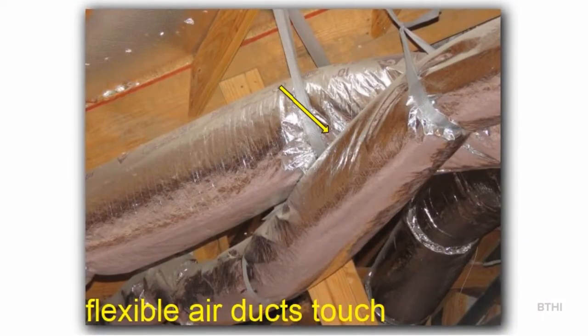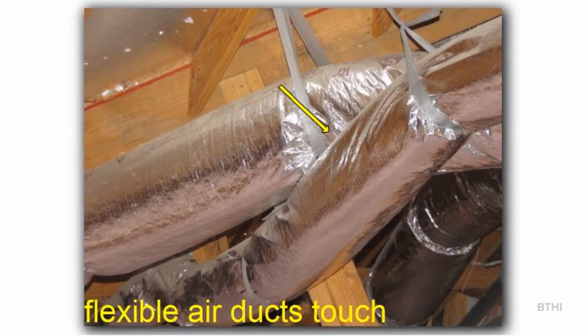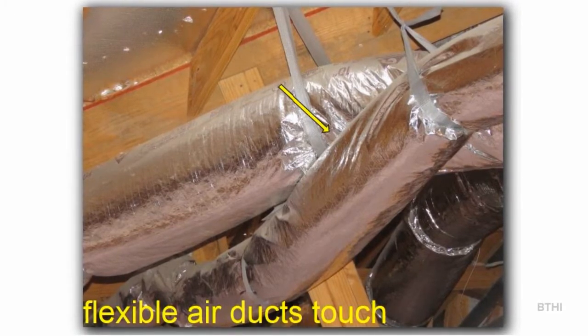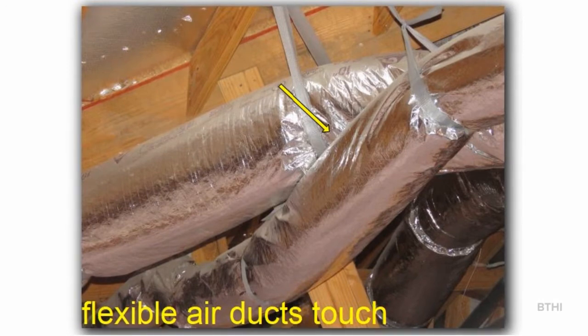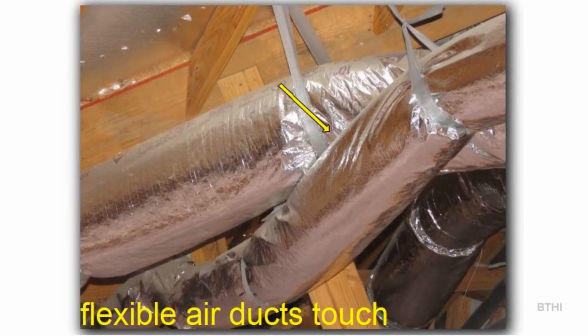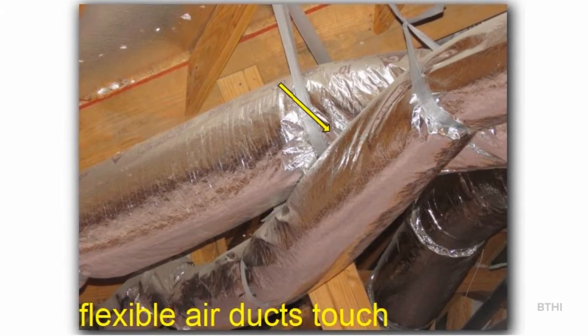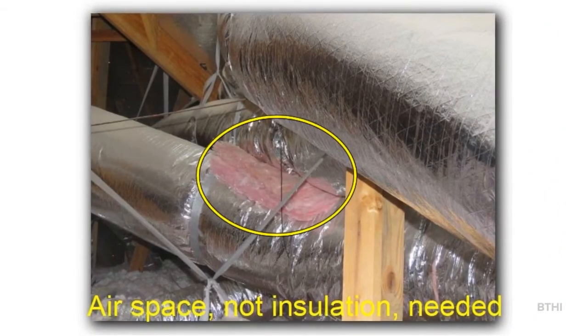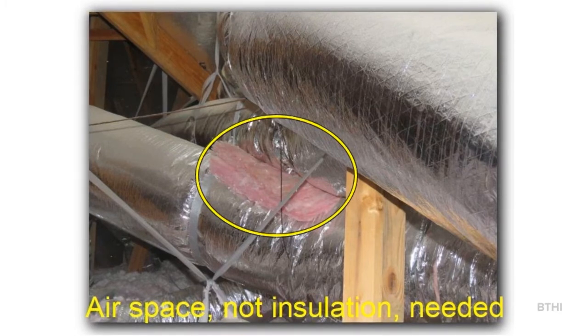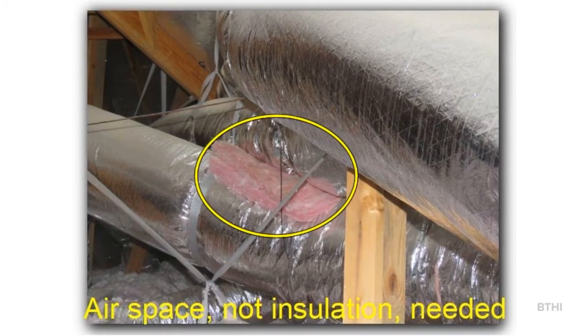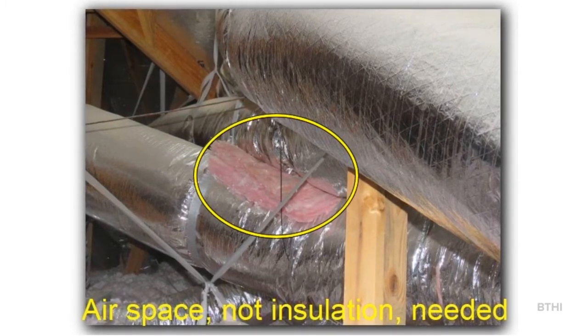Condensation is a natural byproduct of cooling warm, humid air, and several parts of an AC system can cause it or let it get out of control. This video shows some common problems and a few not so common problems. In short, flexible ducts should be installed as straight as possible with no sags or sharp bends or kinks, and they should not touch.